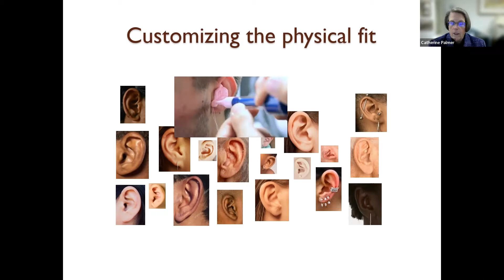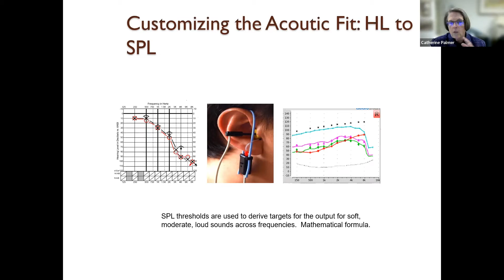And then we individualize the acoustic fit. So this is just showing you a picture of the kinds of measurements we make. But what we're taking on the left-hand side is the hearing results. That's an audiogram. So on the top, across the top from left to right are all the pitches, all the frequencies we hear. And then it goes from very quiet to very loud sounds. So we're mapping the sensitivity of that person, how loud we have to make sound. And on your right-hand side, we flip that graph and set it up so we can put a microphone in the ear, measure the output of a hearing aid, and tune it so we can bring sound back to where the person can hear.